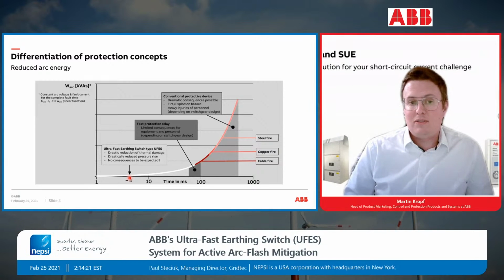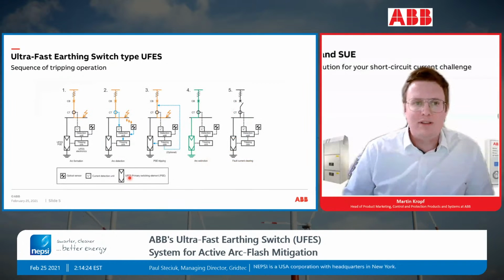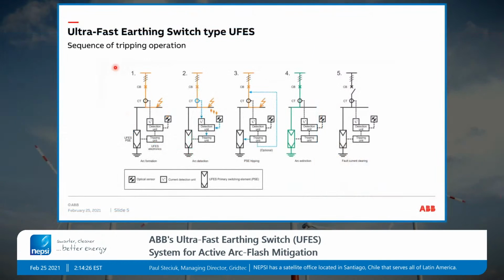How it's going to work, I would like to show you shortly on this slide. You see here, let's assume it's a bus bar. It's an incoming or a feeding. Normally in a switchboard, this is an incoming panel, and then we have here, let's say, the system installed. We have here the UFES, the ultra-fast earthing switch, PSE. It's the primary switching element, which is actually an isolator in normal mode, so it's open. We have the detection electronic, we have the tripping electronic. These are in place here.